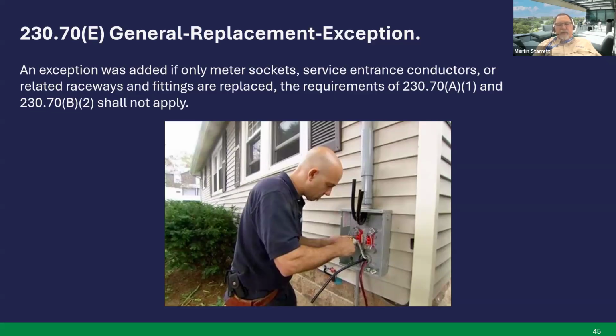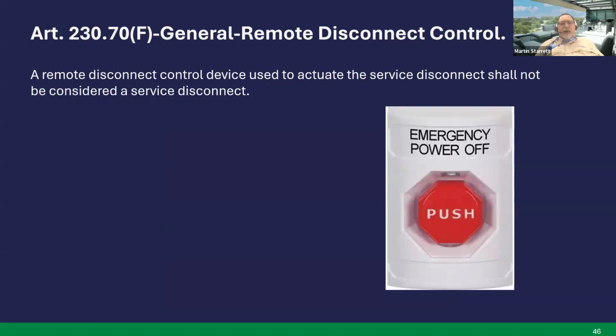This is the National Electrical Code. Check with your utility company. They may have other requirements. Next slide. Article 230.70(F), general remote disconnect control. We have this article now that says that a remote disconnect control device used to actuate the service disconnect shall not be considered a service disconnect. So if you're using one of these little EPO switches as your service disconnect, you will not be allowed to do it in the 2026 code.